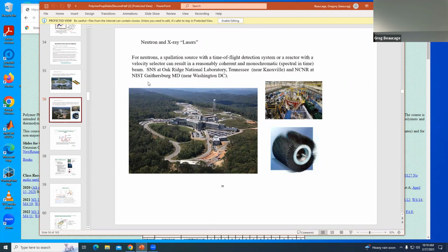And then if you're doing something like inelastic scattering, you need monochromatic neutrons to see the spread of the energy. So they have this thing called a chopper, right? The neutrons' energy is related to their velocity. If you spin this chopper at a certain velocity, there'll be a window open for certain energy neutrons to fly through. It's like a vane thing. So say this thing's spinning at 10 miles an hour and you're going 10 miles an hour, then that hole will be able to follow that path straight through. If it's going 11 miles an hour, it'll hit the wall.